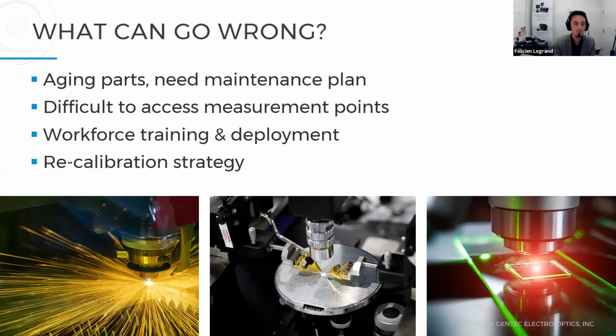And then you need to train your workforce and to deploy and to come up with a recalibration strategy, for example, both for the laser system, have it measured, and for the measurement tool itself. Because the measurement tool for high-powered applications like this is mostly based on thermopile detectors, thermal effects. So that again has to be recalibrated. We usually recommend to get such detectors recalibrated on a yearly basis, but that depends on your application. And since we all know with COVID-related restrictions that traveling is more tricky than ever, come up with the right strategy to send people on site if needed is really important.